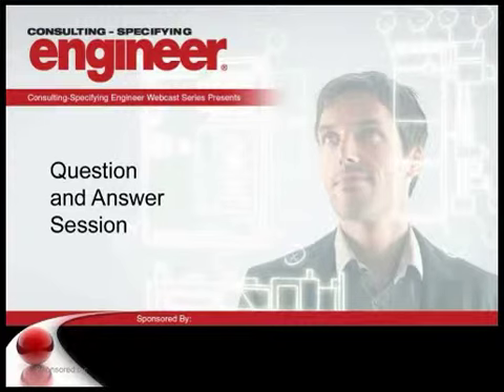Okay. We've got time for one more question or comment, and we're going to take it from Mike Wysocki from Michigan, who's saying Article 705.16 indicates that, quote unquote, consideration shall be given to the contribution of fault currents from all interconnected power sources for the interrupting and short circuit ratings of equipment on interactive systems and includes generators. So by the code, do you not have to consider utility and generator when overlapping neutrals? Jim? I was hoping you were going to say Dean, but I think that same question has been asked 3 times now, and that's an open debate.